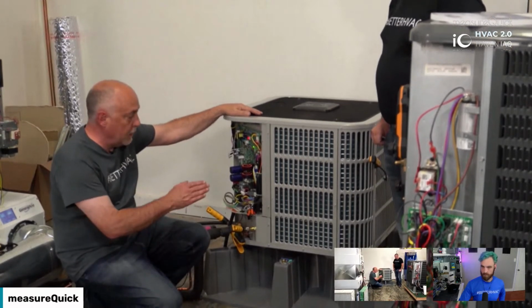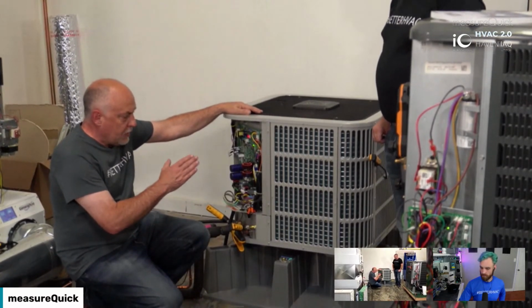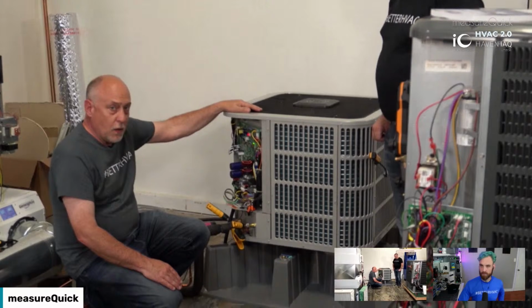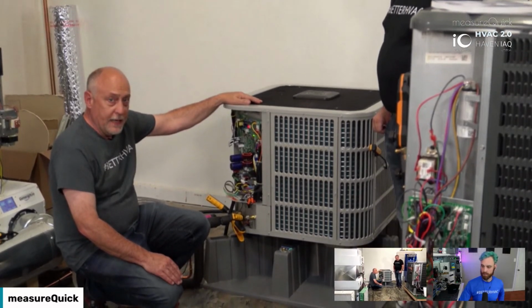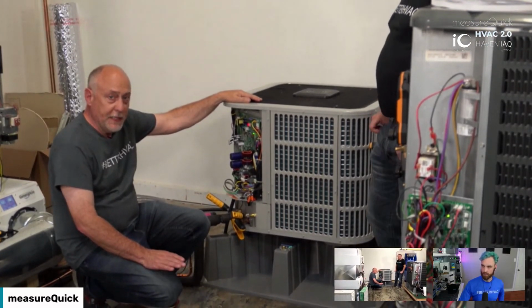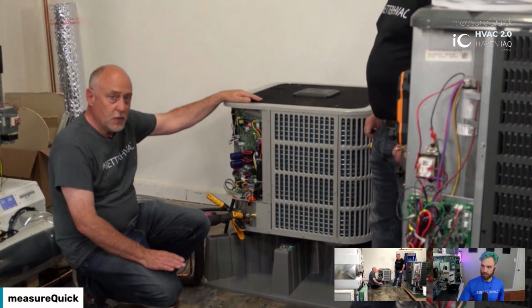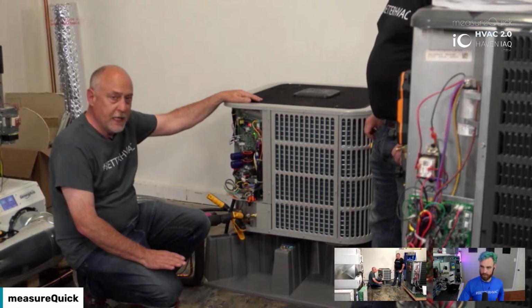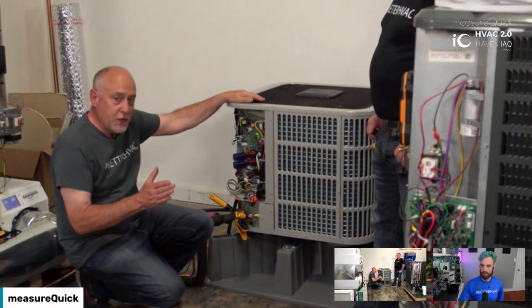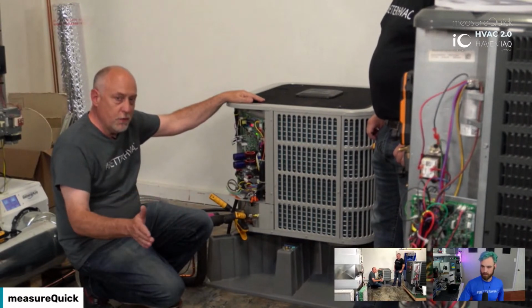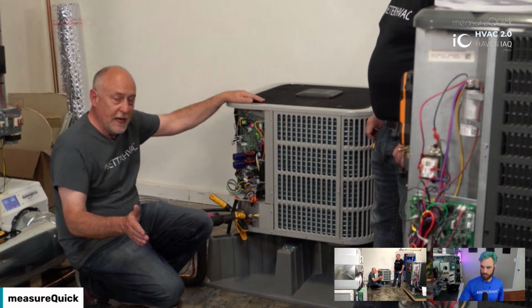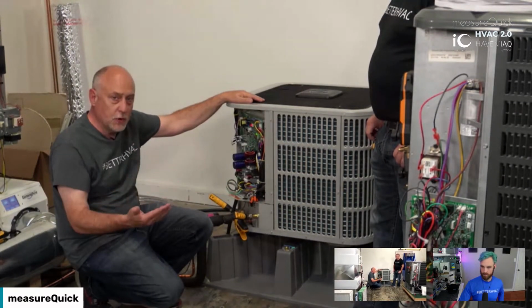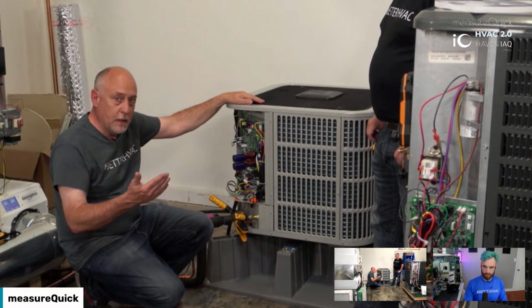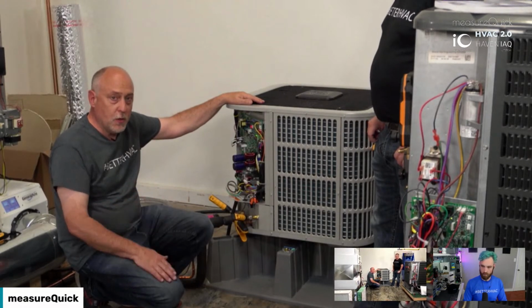In fact, the Bosch unit's pulling out in about an hour what the dehumidifier pulls out in a day, because we have a huge amount of coil space on there. We got the airspeed set low, so we can do a lot of dehumidification really fast. The problem with just relying on the Bosch unit on its own for humidity control is that once it's evening and the warehouse cools off, or the shop cools off, we don't have enough sensible load to control our latent load.